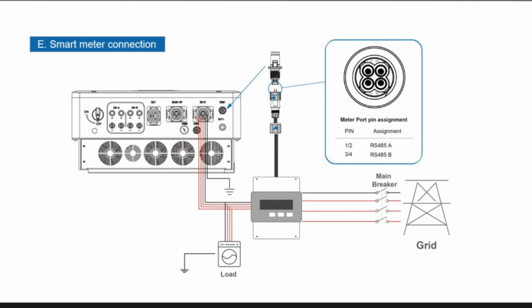I don't know whether there is an actual limit. On these, going back for a moment to the CTs, because these are digital CTs on the single phase, we've actually connected one of these up onto a 100 metre drum of cable to try it, and it still works, which is quite good. Sorry, your question? My customer bought 6 inverters of 30 kilowatts, hybrid, but he now has a problem with the CT, this big one. The wire at the grid entrance is too large and he couldn't pass the wire inside the CT.